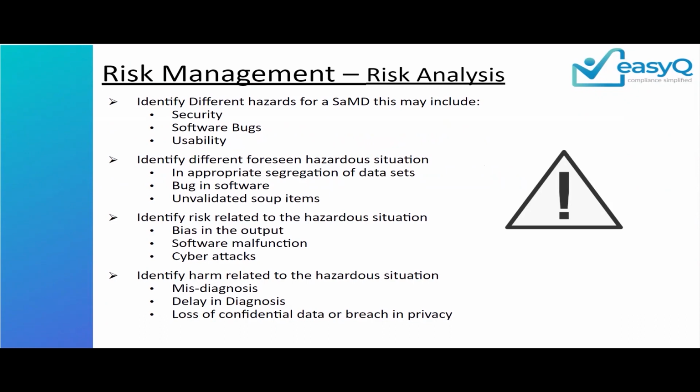Your hazard can be cybersecurity. Your hazard can be that your software itself was not working, so software bugs. Your hazard can be usability. How come you not think about usability? Well, if you have a user interface, and the definition of UI is actually not just something on software that you see. If your product gives a final output as a report, which the doctor is going to look into to gain some information, even that report that you print and give to the doctor is also something that you should think about from a usability perspective. So your hazards can be your security, your software bugs, usability, and your overall functionality of the software.